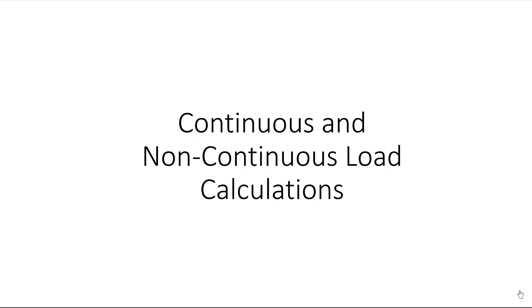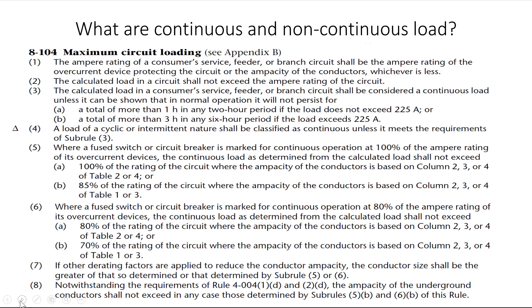Today we will be working on how to size conductors for both continuous and non-continuous loads. First, let's look at the code rules that help us decide if a load is continuous or non-continuous. Rule 8-104, Subrule 3 tells us that a load shall be considered continuous unless it can be shown that under normal operation it will not persist for more than one hour in a two-hour period. So every load is a continuous load unless we can prove it will only operate for a specific amount of time.